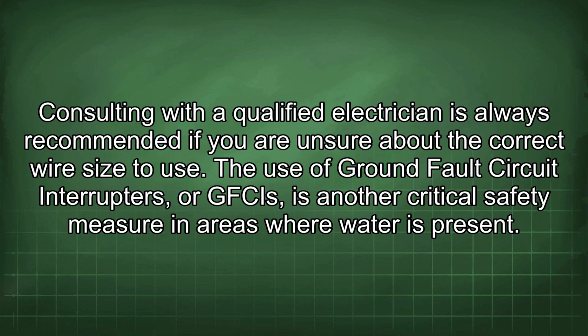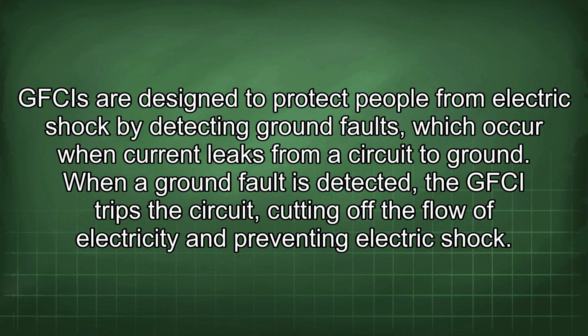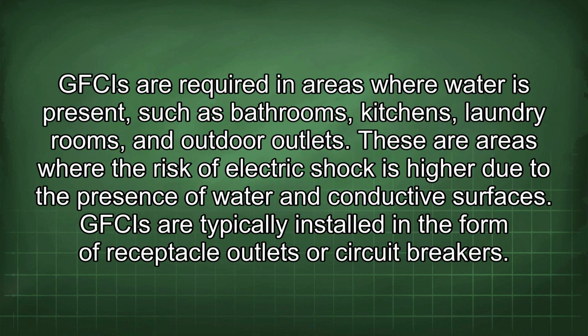The use of ground fault circuit interrupters, or GFCIs, is another critical safety measure in areas where water is present. GFCIs are designed to protect people from electric shock by detecting ground faults, which occur when current leaks from a circuit to ground. When a ground fault is detected, the GFCI trips the circuit, cutting off the flow of electricity and preventing electric shock. GFCIs are required in areas where water is present, such as bathrooms, kitchens, laundry rooms, and outdoor outlets. These are areas where the risk of electric shock is higher due to the presence of water and conductive surfaces. GFCIs are typically installed in the form of receptacle outlets or circuit breakers.